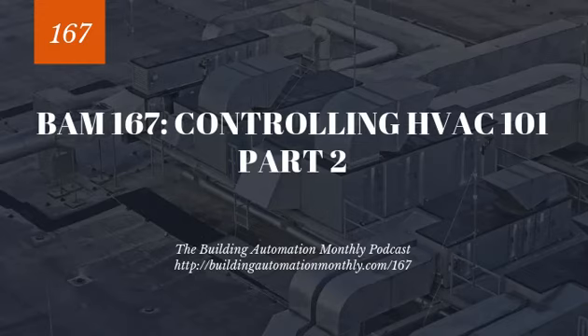So looking at this again, let's take a basic rooftop, right? Or let's take something a little more complex than that. Let's take a mixed air air handler. Mixed air meaning that you have return and you have outdoor air, and the two mix in a mixing compartment or a mixing section. And then that mixed air hits some coils, and then it hits a fan, and then it goes down the supply duct or the discharge duct, depending on what you want to call it.